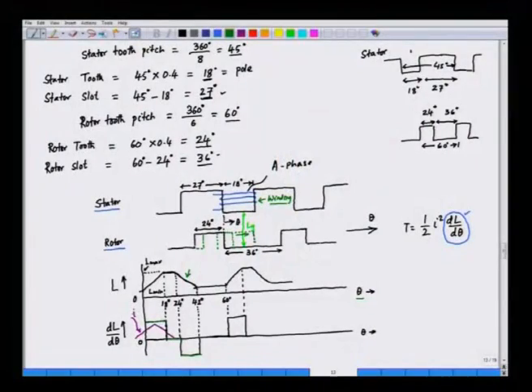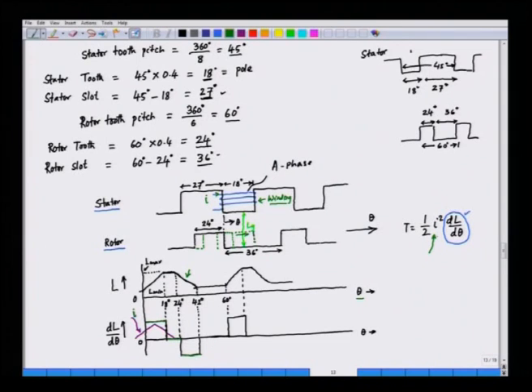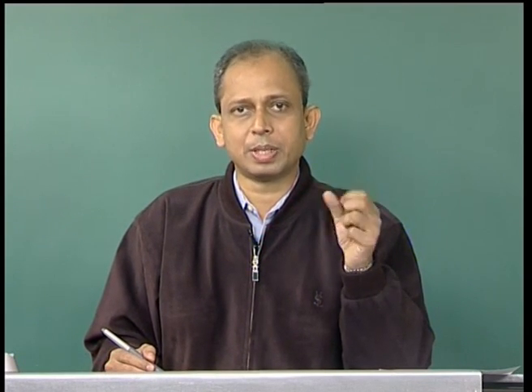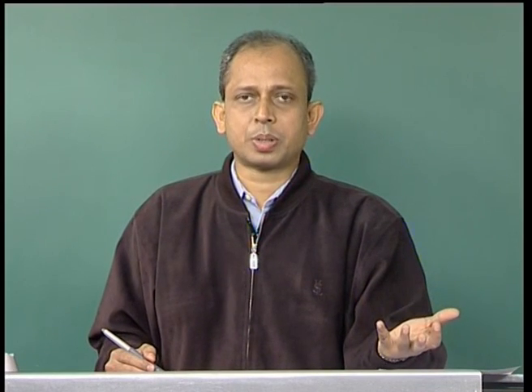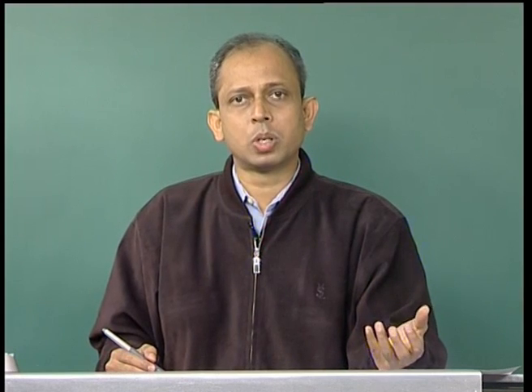For positive torque, the current should be concentrated during the positive dL/dθ region. The phase current should exist predominantly during positive dL/dθ, not during negative dL/dθ — because if the current exists during negative dL/dθ the torque will be negative. Since i² is always positive, for positive torque i² should only exist during positive dL/dθ. That is the principle of torque production in a switched reluctance motor: the current must be optimally switched so it only exists during positive dL/dθ, maximizing torque per ampere.